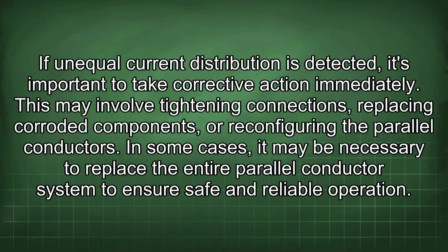If unequal current distribution is detected, it's important to take corrective action immediately. This may involve tightening connections, replacing corroded components, or reconfiguring the parallel conductors. In some cases, it may be necessary to replace the entire parallel conductor system to ensure safe and reliable operation.